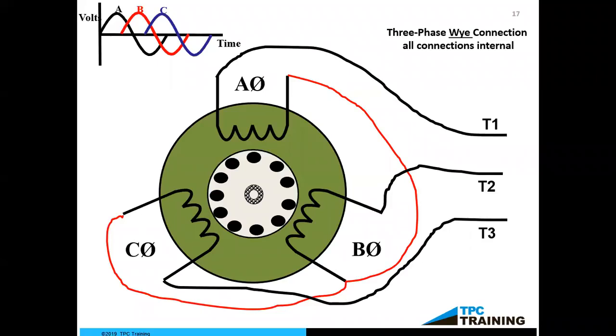And many times, and a lot of people don't realize this, but that short circuit current can get up to 20, 30, 40,000 amps, depending on the size of the wire and the size of my transformer. And that's what causes an arc flash explosion. So we definitely want to make a determination if those windings are shorted with each other, because if we don't, we are going to definitely have the capability of causing some type of injury to ourselves or damage to more equipment that might be around this motor.